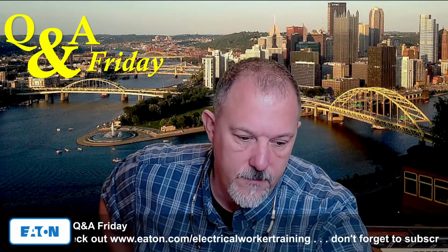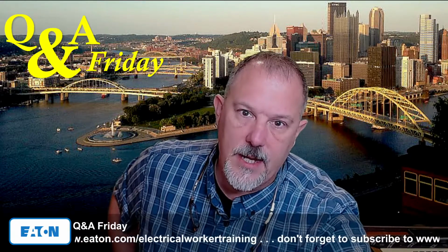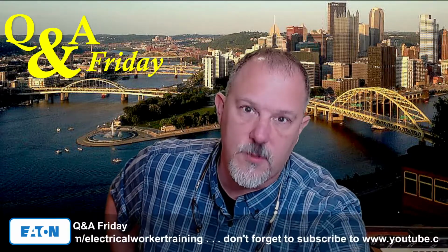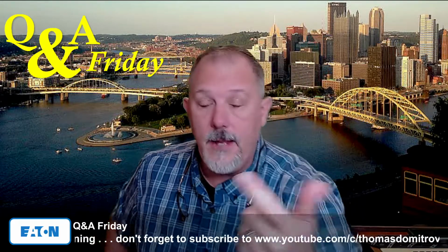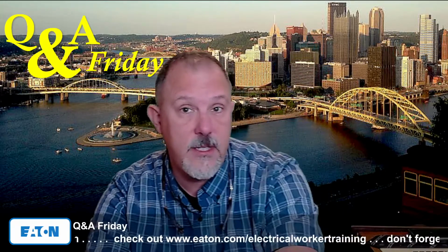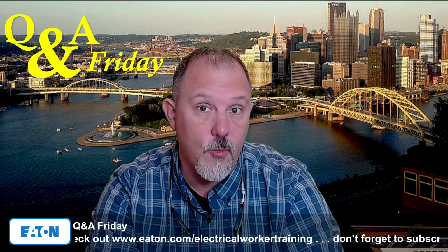All right, so you put these breakers into an enclosure, right? And we know one of the hardest tests to pass from a standards and codes perspective in making assemblies is that heat rise. They put temperature sensors inside and on certain locations on the circuit breakers, and they look for the temperature rise as it carries current, and it can't exceed certain thresholds. And I'm telling you, that's why we have the 80% versus 100% rating, right?